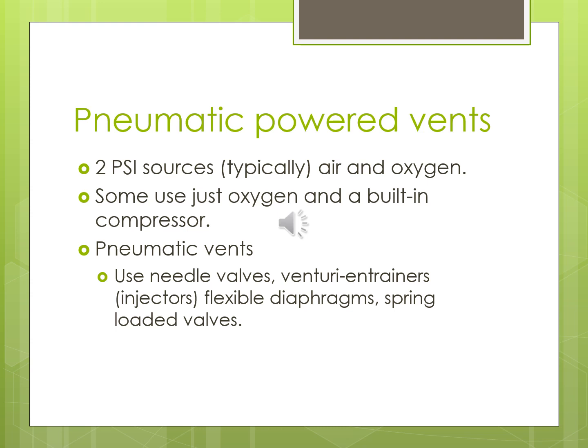Pneumatically powered vents — and this applies to mixed-powered vents as well — typically have two PSI sources: air and oxygen. You can plug other gas sources into the back of most ventilators, but check your manual to see what yours will accept. Some use just oxygen with a built-in compressor that bleeds the oxygen in and blends it to give you the desired FiO2. Pneumatic vents can use needle valves, Venturi entrainers, injectors, flexible diaphragms, and spring-loaded valves.